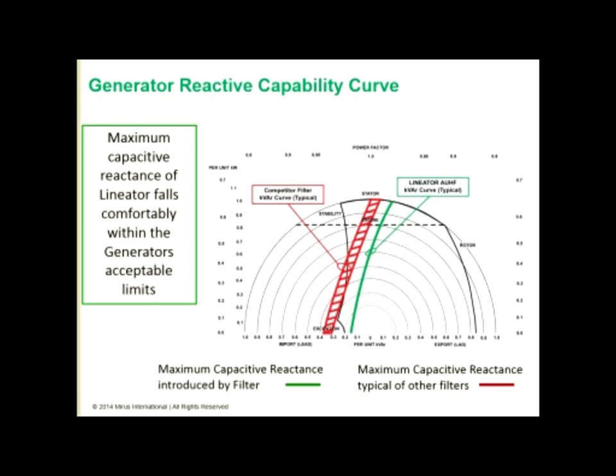For this generator, the envelope shows that at no load, reactive power must be less than 20% leading, but can be as high as 83% when the load is lagging or inductive. The Lineator AUHF reactive power consumption line is shown in green and is comfortably within the generator's capability envelope. The leading power factor of the filter is not a problem for the generator and it is therefore unnecessary to switch out the capacitor under light loading conditions.